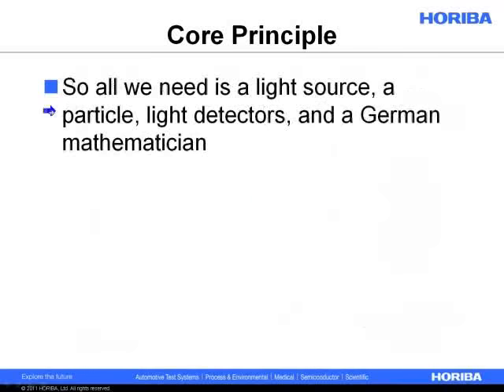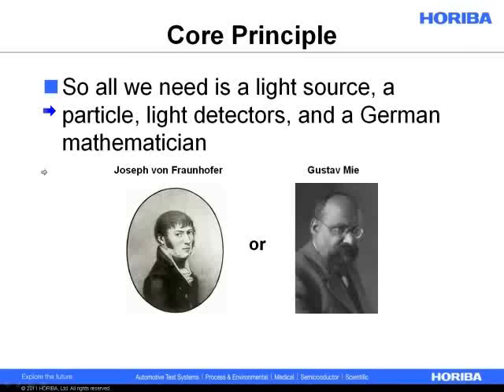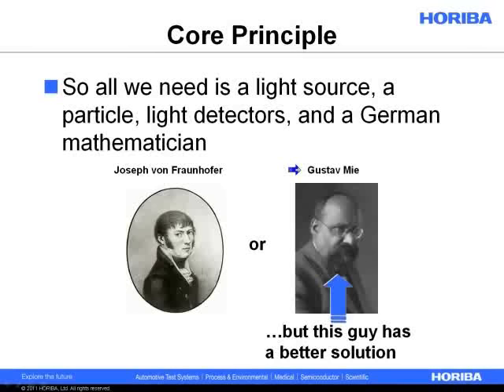All we need to do this measurement is a light source, a particle, some light detectors, and a German mathematician. We can use one of two: Joseph von Fraunhofer, who developed the Fraunhofer approximation, or Gustav Mie, who developed the Mie scattering theory. The important thing to take away is that Mie scattering is ultimately a better solution for most particles. It extends the measurement range down into the nanometer scale, whereas the Fraunhofer approximation starts running out of steam around 20 to 50 microns, depending on the wavelength of light.